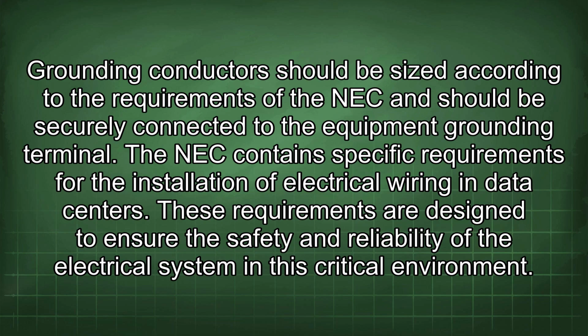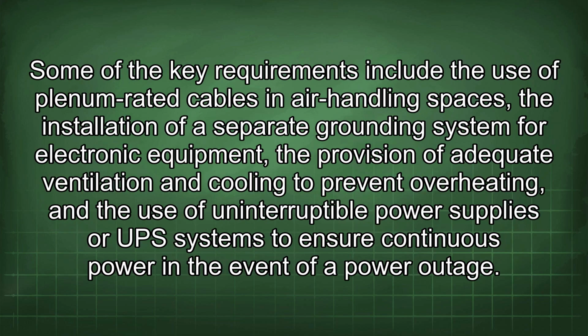The NEC contains specific requirements for the installation of electrical wiring in data centers. These requirements are designed to ensure the safety and reliability of the electrical system in this critical environment. Some of the key requirements include the use of plenum-rated cables in air handling spaces, the installation of a separate grounding system for electronic equipment, the provision of adequate ventilation and cooling to prevent overheating, and the use of uninterruptible power supplies or UPS systems to ensure continuous power in the event of a power outage.